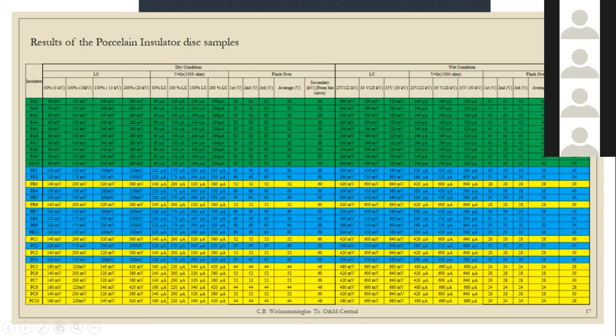So according to the IEC standard, leakage current at 200% should be less than 300 microampere. Between 300 and 350 is the moderate group, and if it is higher than 350, the insulator is bad. For the flashover voltage, if it is higher than 70 kV, it is good. If it is 55 to 70, it is moderate. If it is less than 50, it is bad. So according to my laboratory results, I divided my insulator sample into good, moderate, and bad, as well as the glass insulators.